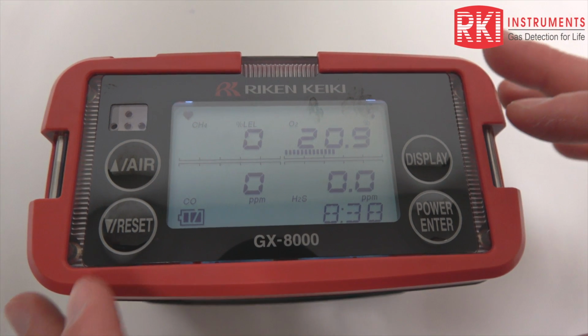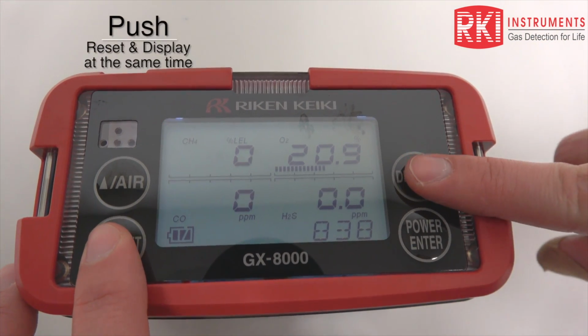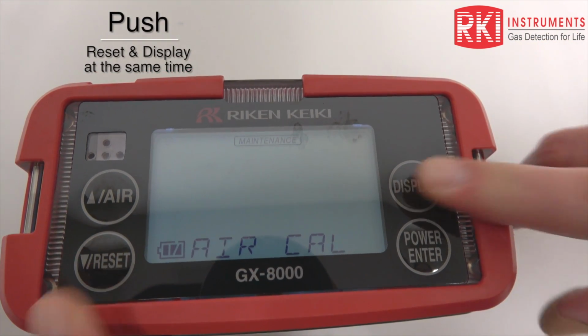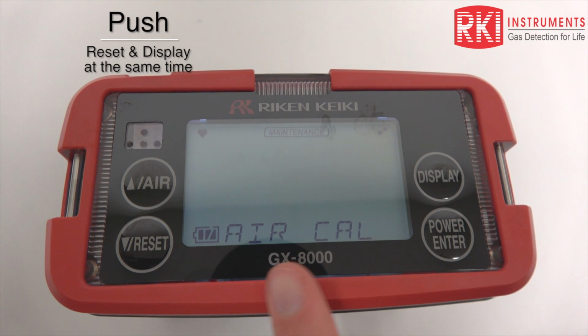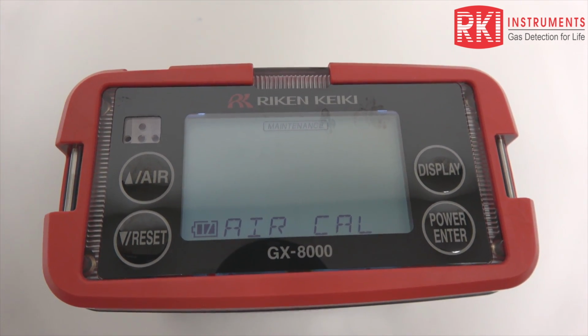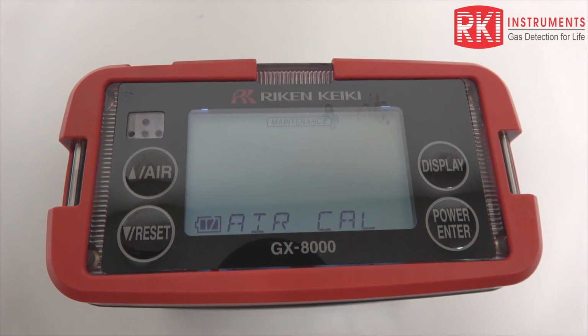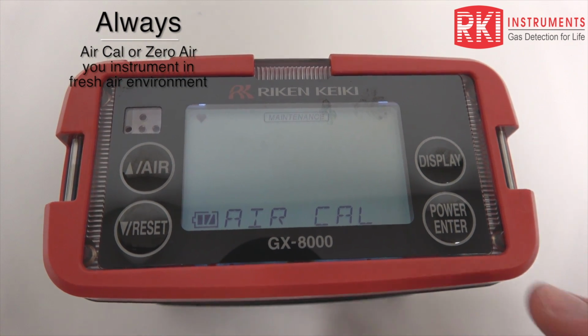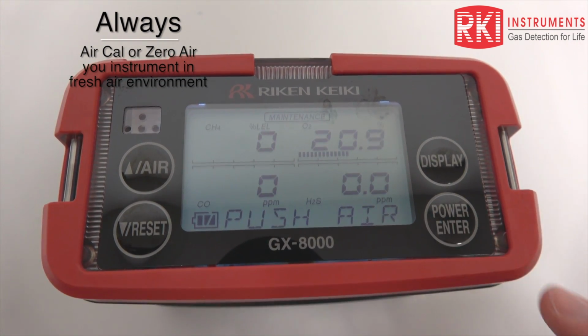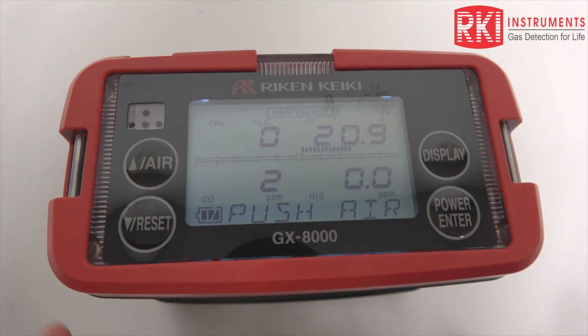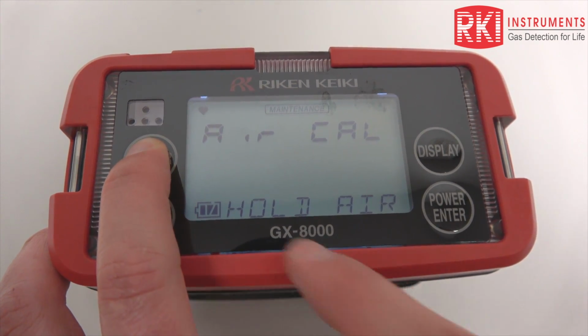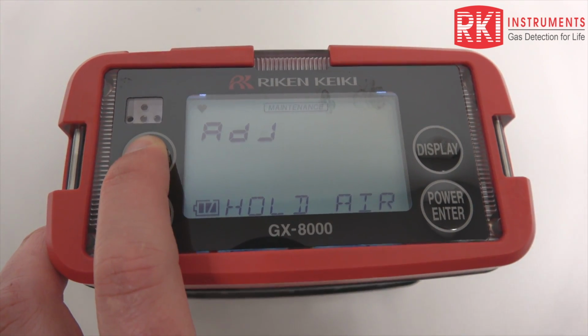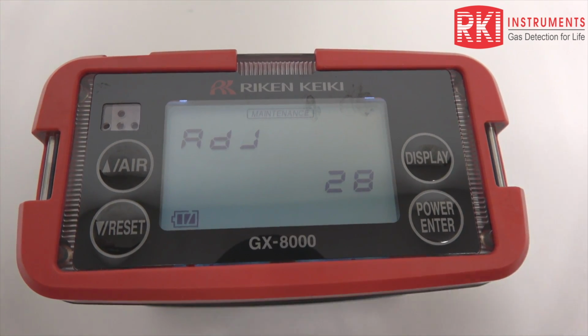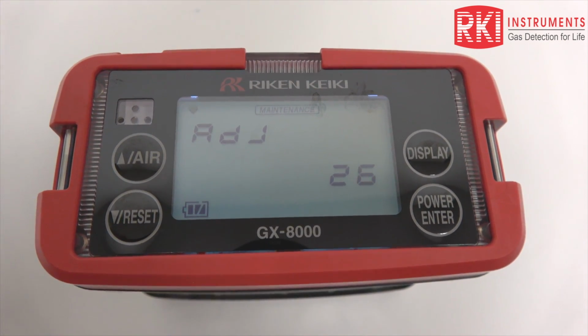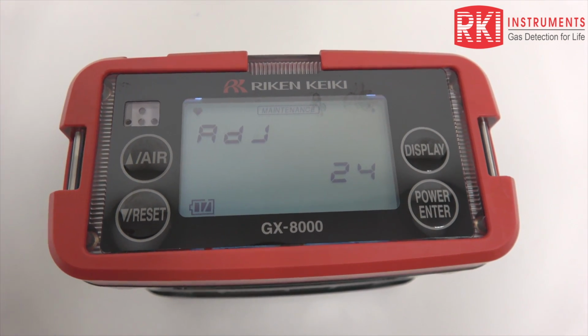To get into calibration mode, use the reset and display buttons, press them both at the same time. Here's our air cal. You need to make sure you're in a fresh air environment. If you're not, you need to find some fresh air or get a cylinder of zero air. We're going to use power enter to get into this menu. It's telling you to push air. So I'll go ahead and push and hold air. It prompts you to hold it, prompts you to release it, and then it counts down from 30 just to give the sensors enough time to acclimate and get a good zero.